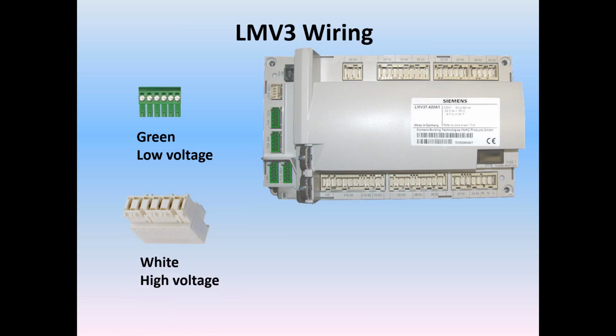We also have green terminals. Those are tight pitch and those are low voltage. All the green terminals are low voltage connections. And then the white terminals have a larger pitch, and those are used for all the high voltage, the line voltage, 120 volts, or in some cases, 230 volts.